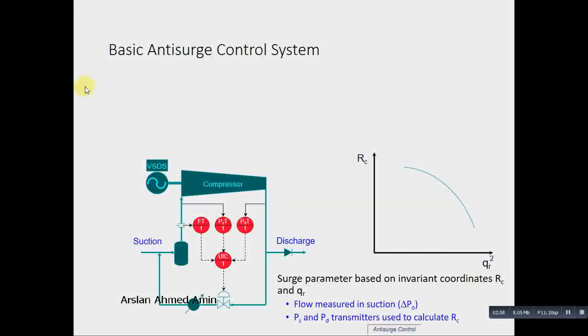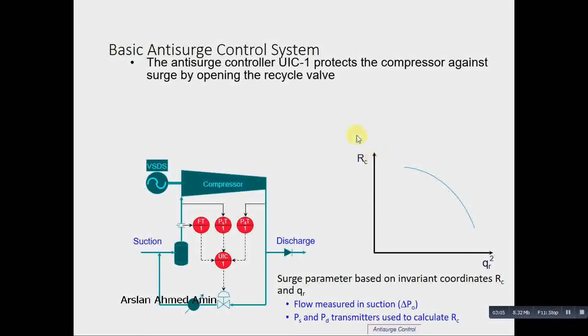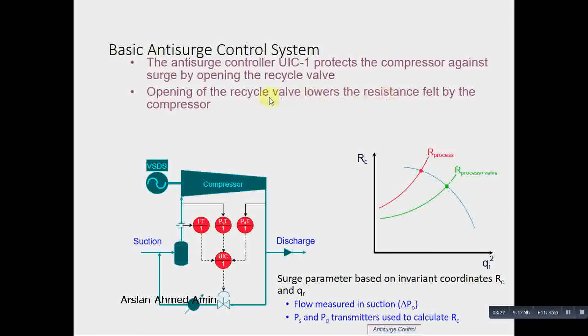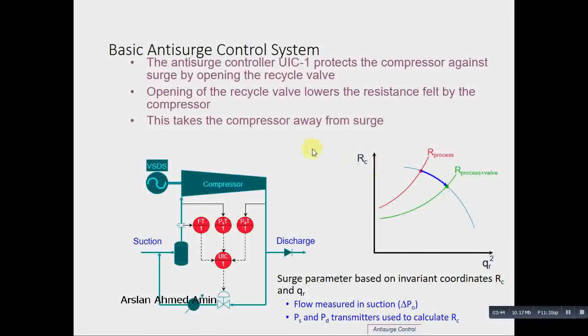This is how the basic anti-surge controller system is demonstrated here. We see QR scale and RC — in this case the RC compression ratio is used, while in the algorithm HR is used. The anti-surge controller protects the compressor against surge by opening the recycle valve. Opening the recycle valve lowers the resistance seen by the compressor, so the resistance decreases, the flow increases, and this operating point moves away from the surge line, taking the compressor away from surge.